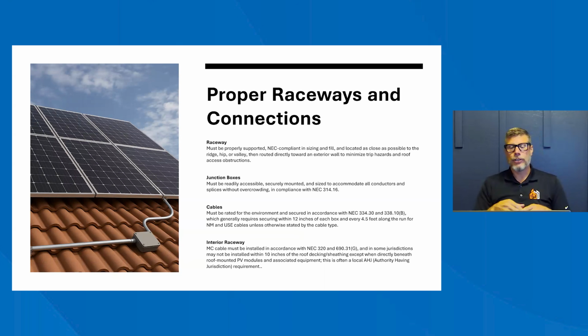Finally, your interior raceways, these are the ones that are in your attic. This PV wiring needs to be secured every 6 feet. You need to make sure it's kept off of the insulation. So if you see it laying on insulation, that's a call out. And you got to make sure that it's not obstructing any vents. Now the raceway is only 3/4 inch pipe or conduit, so chance of it actually blocking a vent are pretty slim, but you don't want it in front of the vent. If it's within reach of a walking area, it needs to be protected for sure. And then here's the big one.